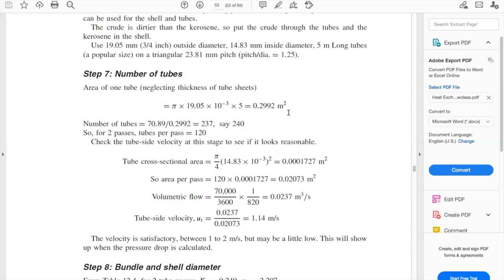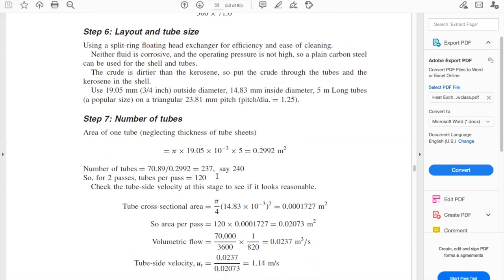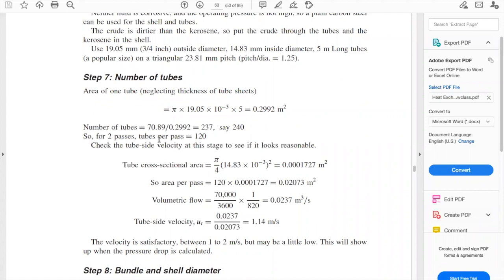We are ready to calculate the number of tubes. The number of tubes equals the heat transfer area A₀ (from step five) divided by the area of one tube (0.2992 m²), giving approximately 237 tubes. Note: there is a typo in the book — it says 70.89 but should be the value we calculated. Since we tend to over-design, we round up to 240 total tubes. With two tube passes, that gives 120 tubes per pass.